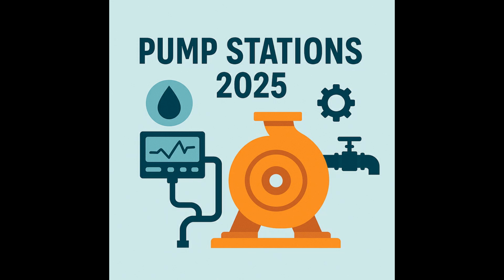Now, what happens when you have multiple pump stations feeding into a single force main? That sounds like it could get complicated, like a traffic jam, but with water pressure. Is that a coordination challenge? It absolutely can be a major coordination challenge. If 2 or more stations discharge into the same pressurized force main without proper sequencing and control, you run a serious risk of causing hydraulic surges, dangerous pressure spikes, or even backflow from one station into another. Not good. Yeah, sounds problematic. So what are the solutions?